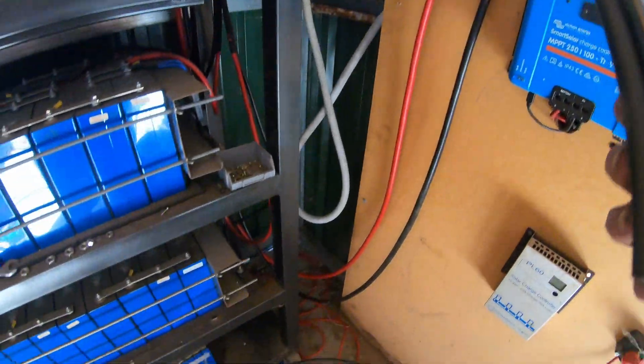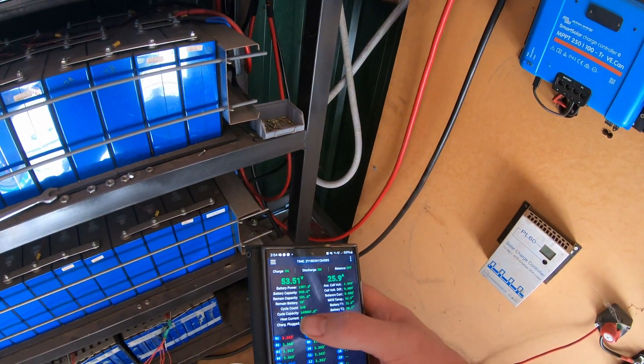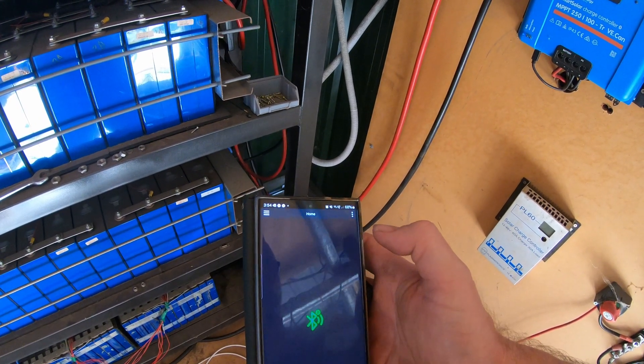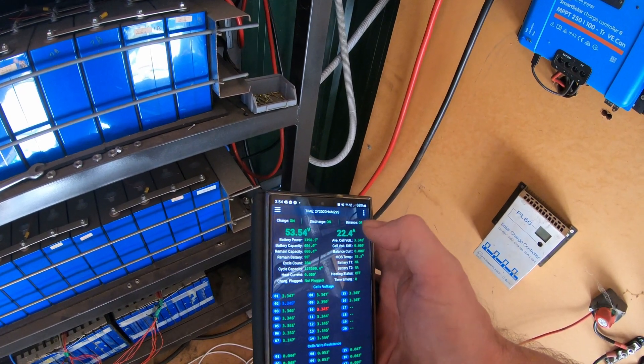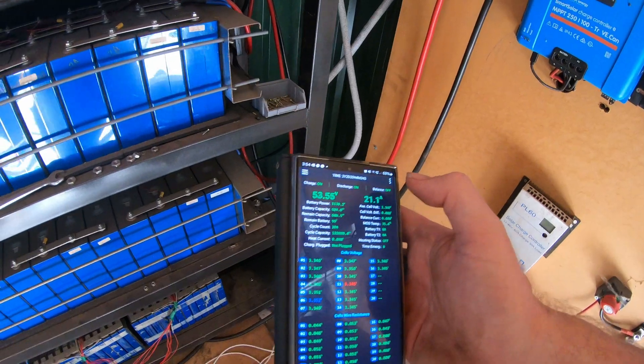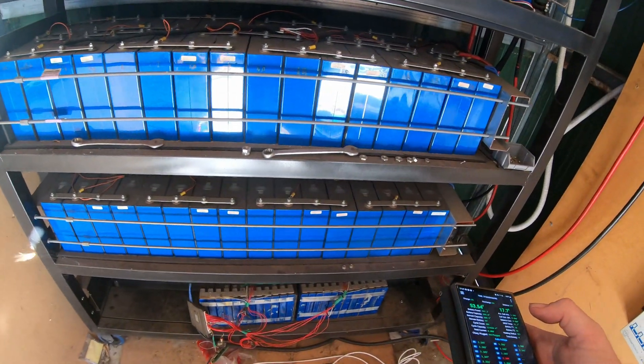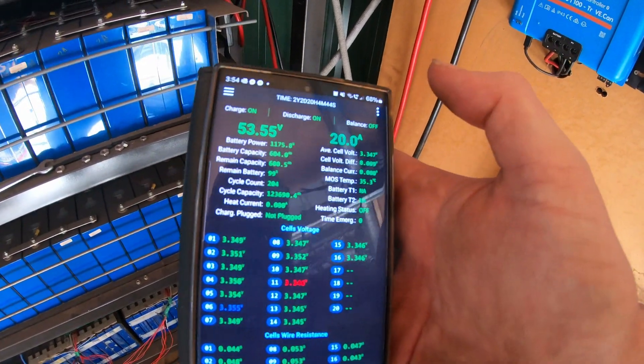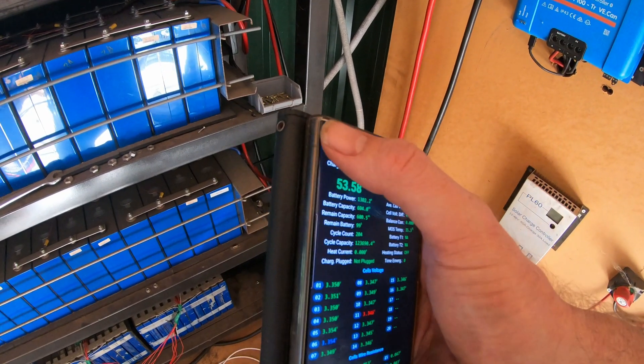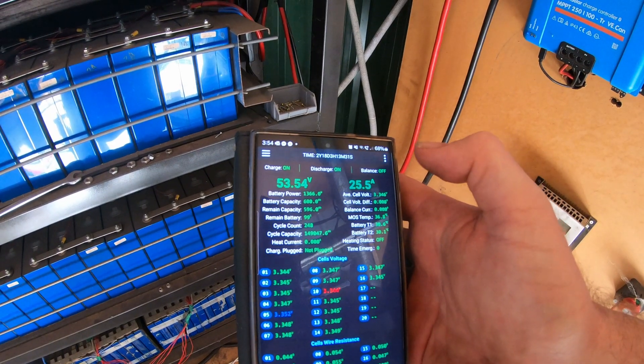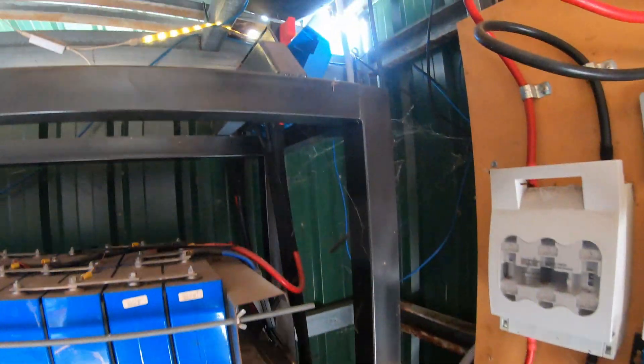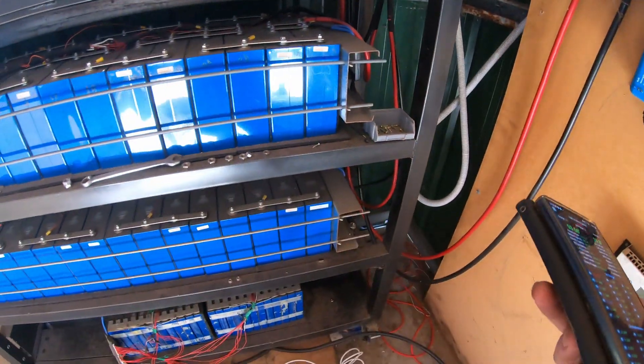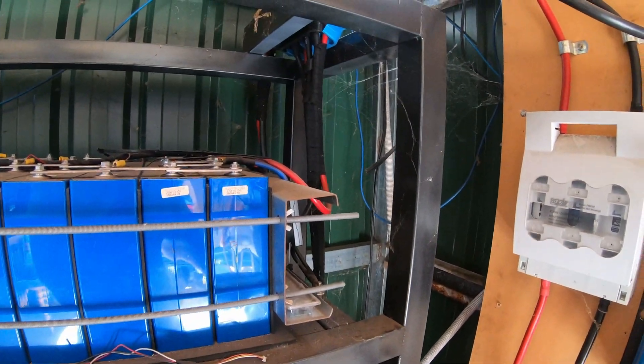Let's get to the bottom of this. So we've got 23.51, 23.54 - that bottom pack is still sitting slightly higher. Maybe is it just that the bottom pack is in better shape because it's newer? Is it maybe that some of the cells - or do we have an imbalance? So we've got bouncing between 19 and 20, 24 amps shelf one. See, 19 and 24, and this one's going 25 and 28. And the only difference is those cables are shorter and those ones are longer. So I thought it was an impedance thing to be honest with you.